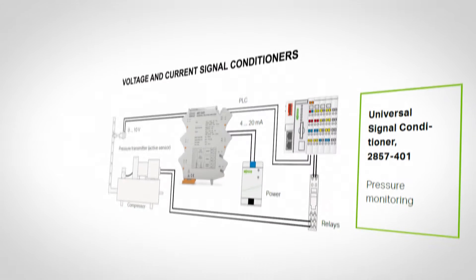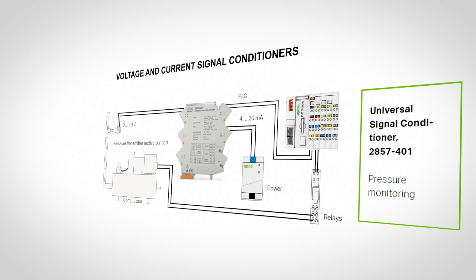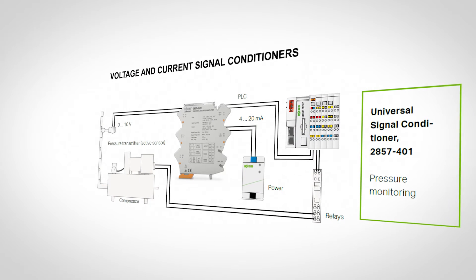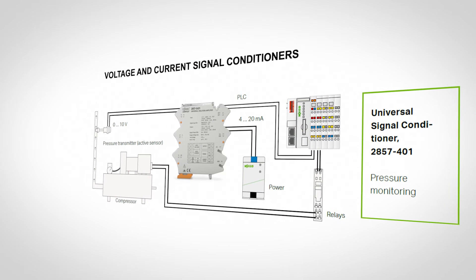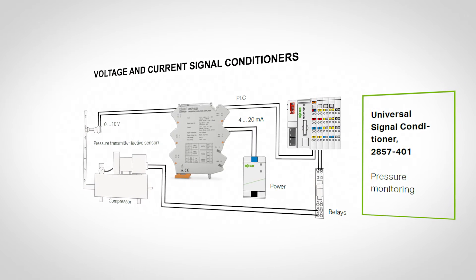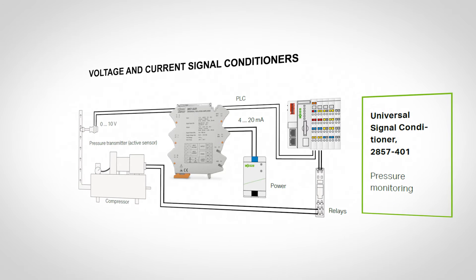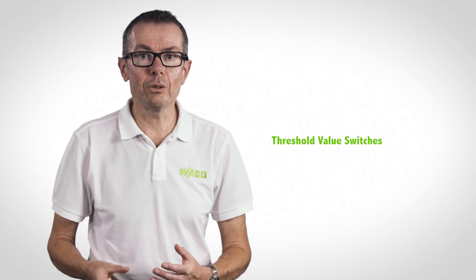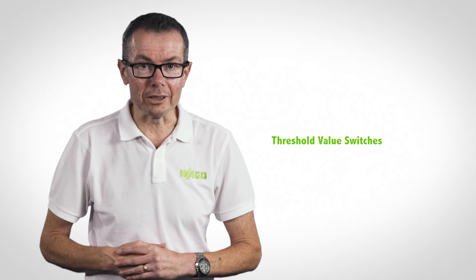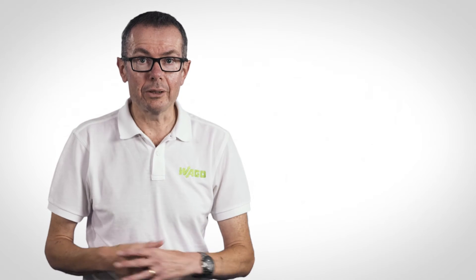Current and voltage signal conditioners: these are simply signal converters. They can be used where, for example, a pressure transducer has a 0 to 10 volt output but needs to feed a PLC that only has a spare 4 to 20 milliamp analog input.